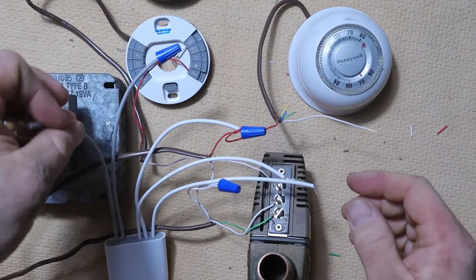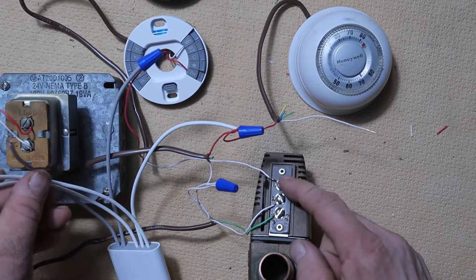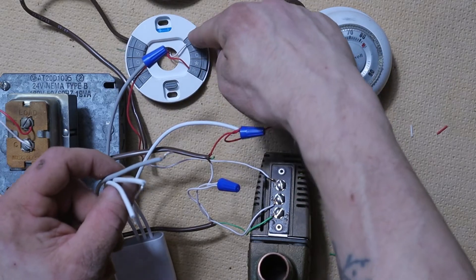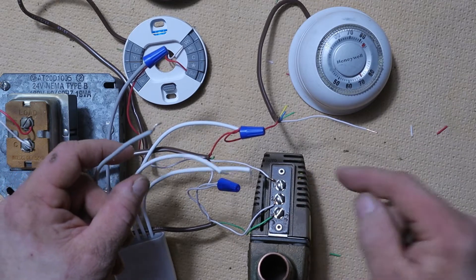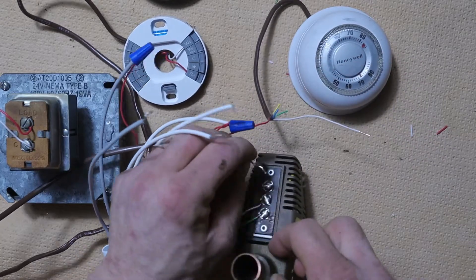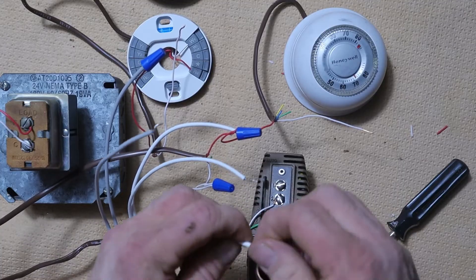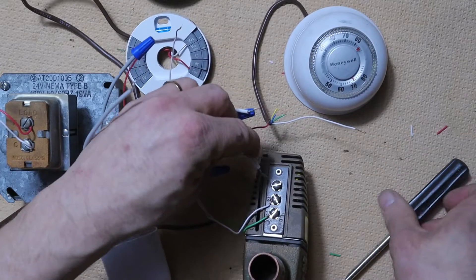Now we're going to go to our Taco zone valve and find terminal number one at the top — that is the power terminal that actually runs the zone valve. The white wire from your W terminal on your Nest thermostat runs down to that number one terminal. We're going to disconnect that wire from terminal one, set it aside, and put the W wire from the right side of our power connector onto that number one terminal instead.